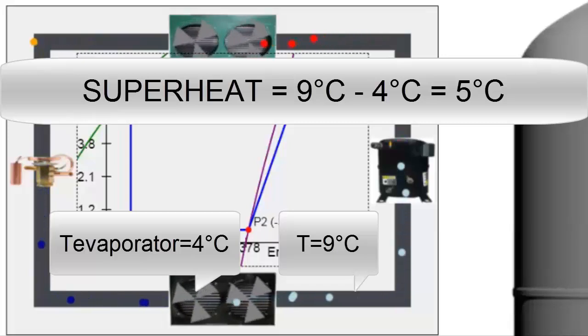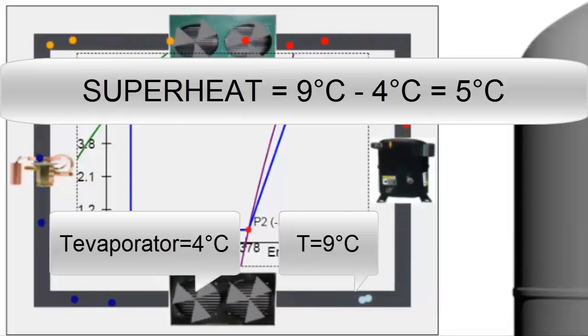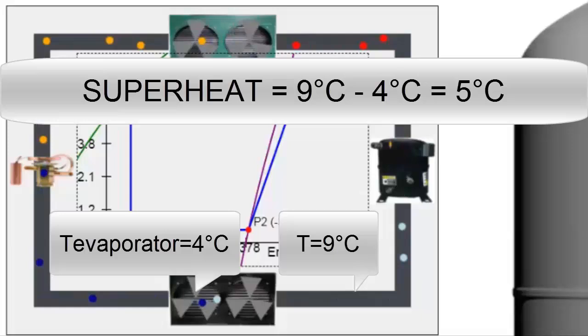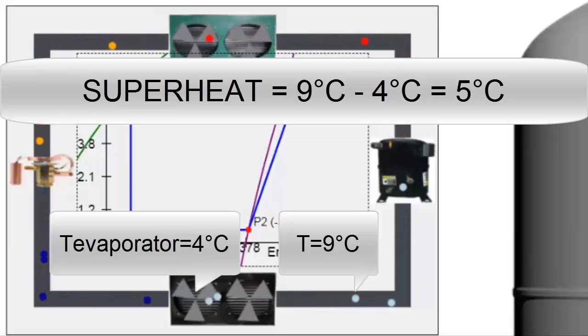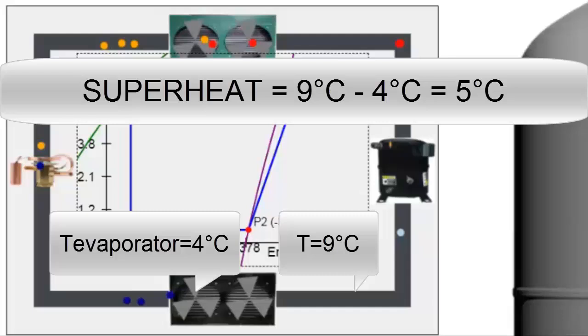The value of superheat varies depending on the thermal load of the air conditioning system. For example, in a room or space with many people, superheat may exceed 5 degrees Celsius, while with a lower thermal load or fewer people in the room, superheat will be below 5 degrees Celsius, even reaching as low as 0 degrees Celsius when the cooling demand is minimal.